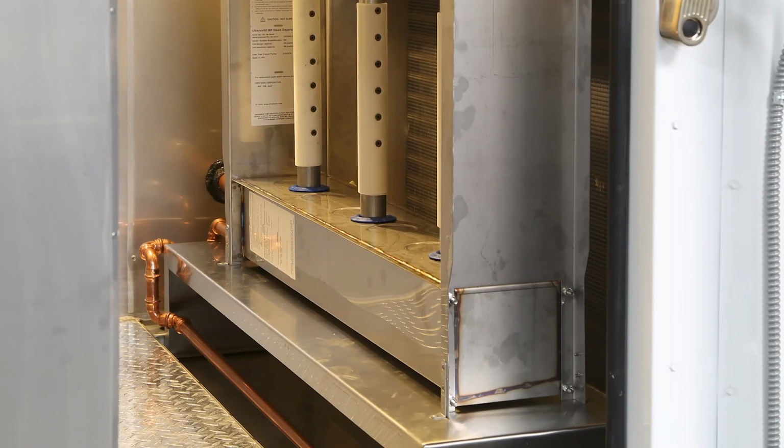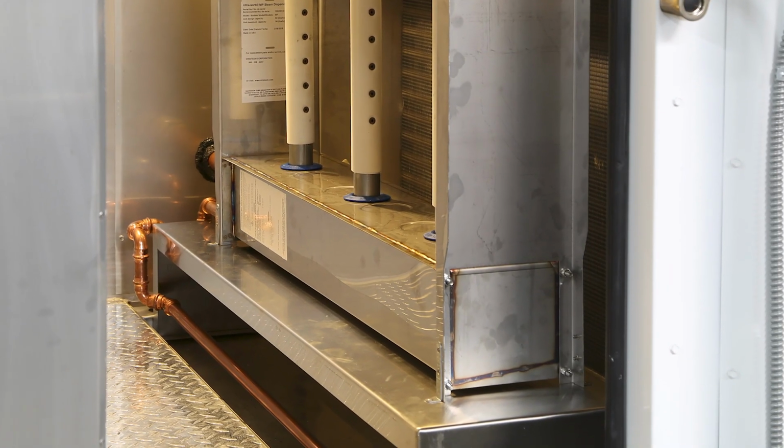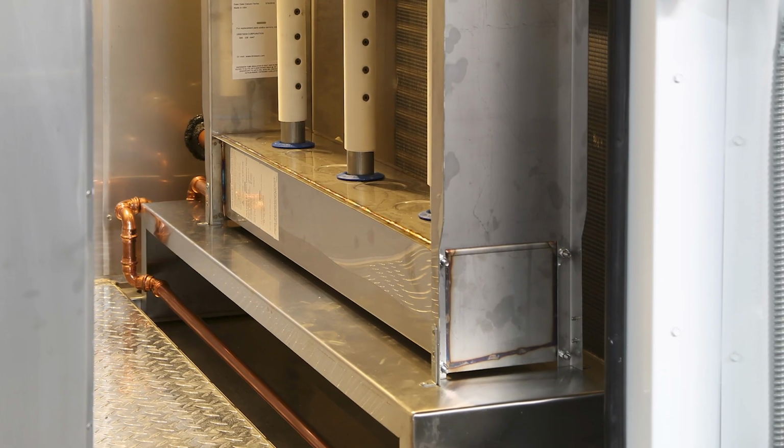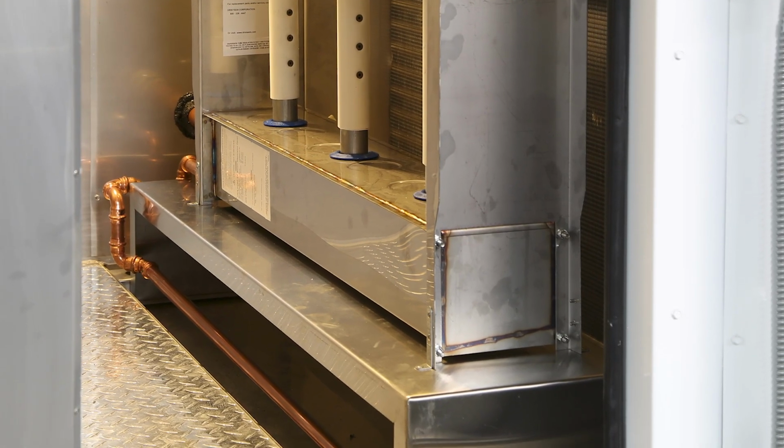If you let the air go underneath the panel, that bypass, you reduce your pressure drop. But there's a consequence, because you have less volume of air that you're adding moisture to initially. So it's a balance between these different things, and knowing what space you have available will drive that a bit. Make sure you're considering that pressure drop and taking into account the system effect, potentially with a blank off panel.